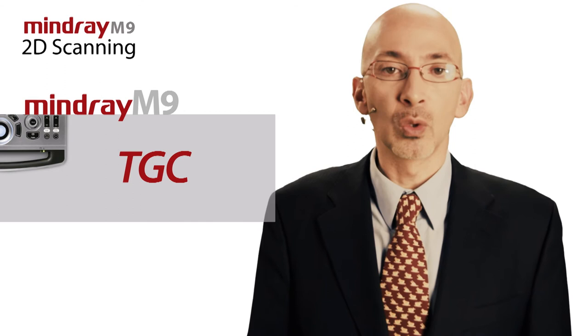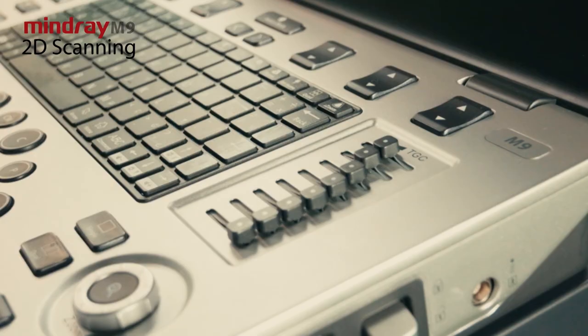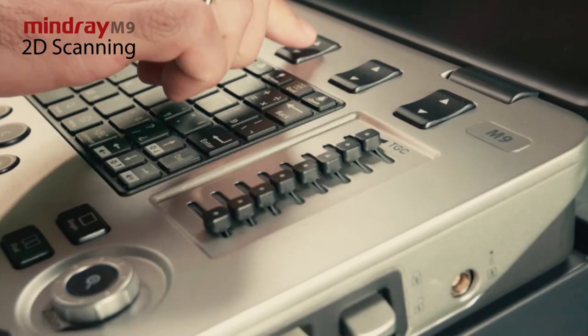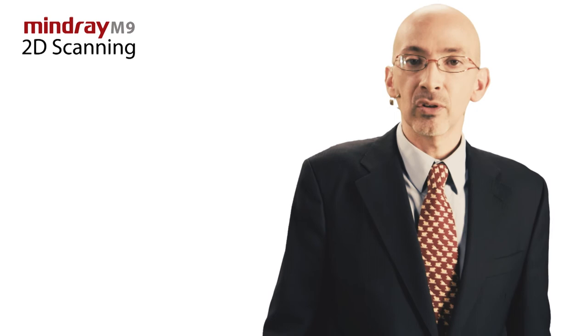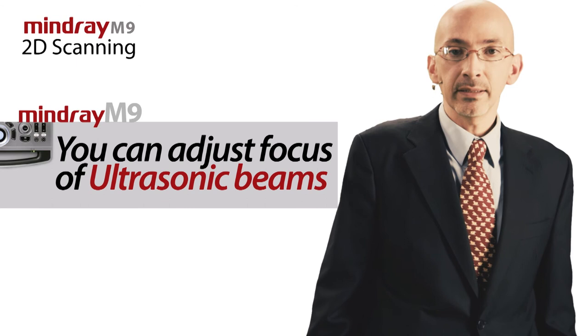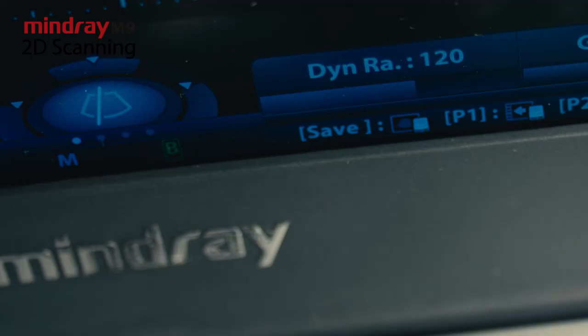TGC. The system compensates the signal from the deeper tissue by segments to optimize the image. There are 8 segments TGC sliders on the control panel corresponding to the areas of the image. You can adjust the focus of the ultrasonic beams using the symbols which are displayed to the right of the image. Dynamic range. This function is used to adjust the B image resolution to compress or expand the gray display range. The real-time values are displayed in the image parameter area in the top right corner of the screen.